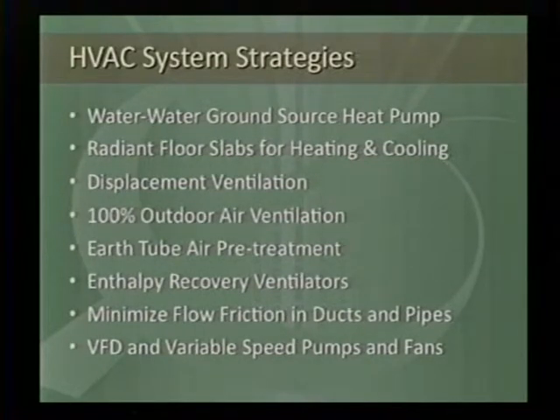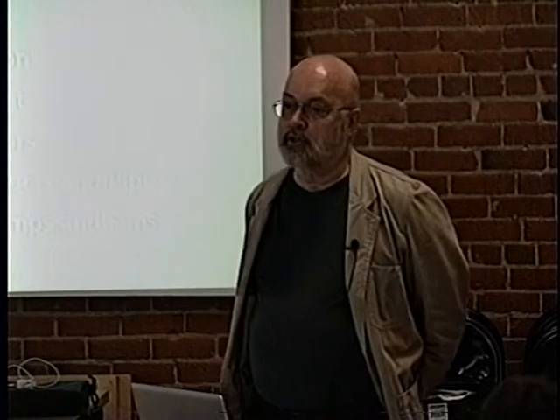HVAC strategies. This building uses a water-to-water ground source heat pump that generates hot water in the winter and chilled water in the summer. It's a seasonal changeover system. In the shoulder seasons in spring and fall, we've got operable windows and we've got some wood-burning stoves. So there are different ways to provide cooling and heating in that kind of a changeover system. The radiant floor slabs are used for heating and cooling. It's now becoming my experience, as I do more of these buildings, that it is appropriate to provide the sensible heating and cooling loads using basically the mass of the building and radiant sources for the sensible side, and use air for the ventilation requirements and the latent portion of the load.